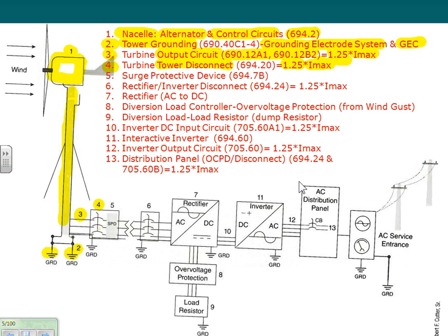The most important thing about the disconnect is that it's on the tower or somewhere on the building where you can see it from the tower. One other thing, since we have 5 minutes for this session, we're not going to be able to go through everything. One very important thing about the disconnect is speed control of the turbine. One way of controlling the speed is to take a feedback from the output back into the turbine. If that's the way of controlling the speed, they don't want you to disconnect the output circuit, because if you disconnect it, the turbine goes out of whack, starts spinning and destroys itself.